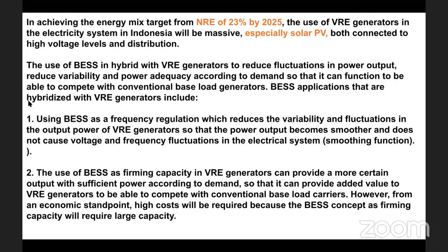BESS applications that are hybridized with VRE generators include: first, using BESS as frequency regulation, which reduces the variability and fluctuation of the output power of VRE generators, so that the power output becomes smoother and does not cause voltage and frequency fluctuation in the electrical system; this is the smoothing function. Second, the use of BESS as firming capacity in VRE generators can provide a more certain output with sufficient power according to demand, so that it can provide added value to VRE generators to be able to compete with conventional baseload generators.